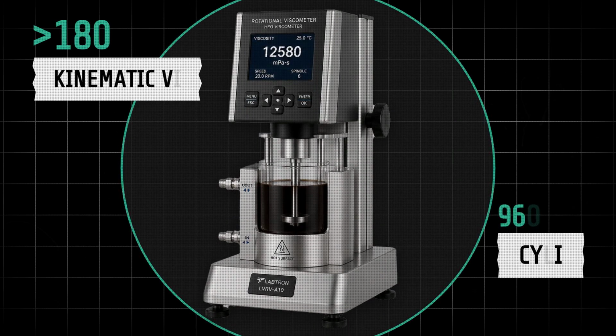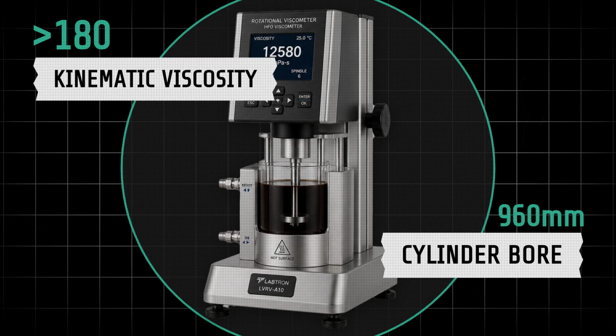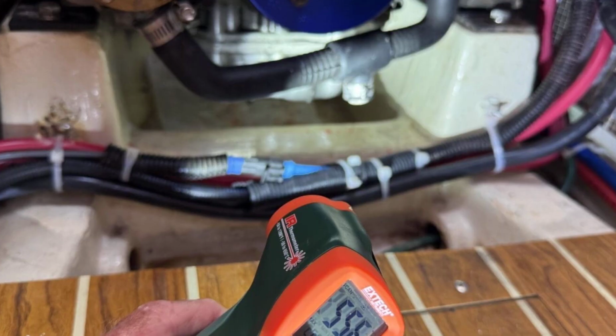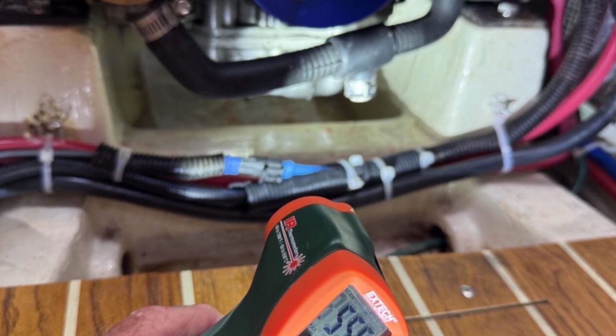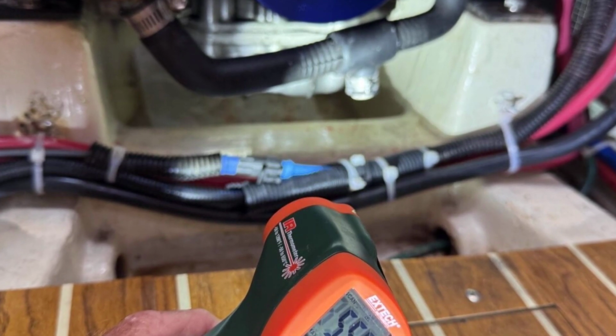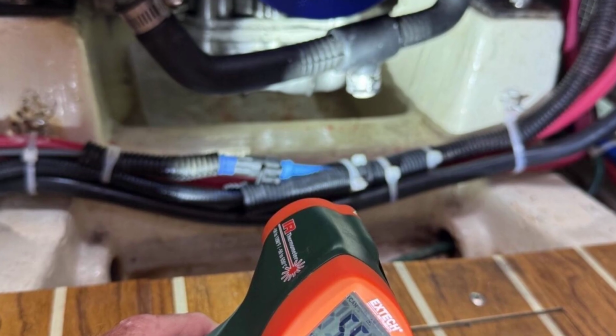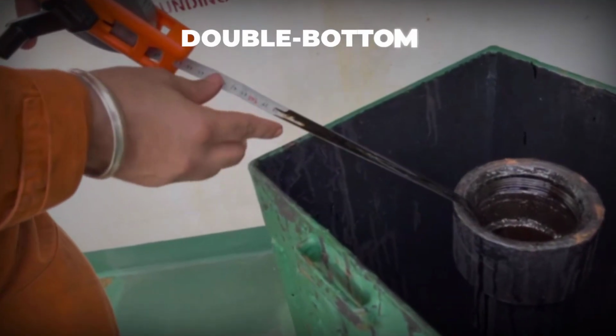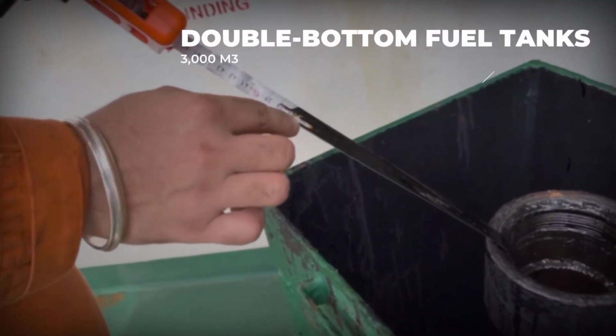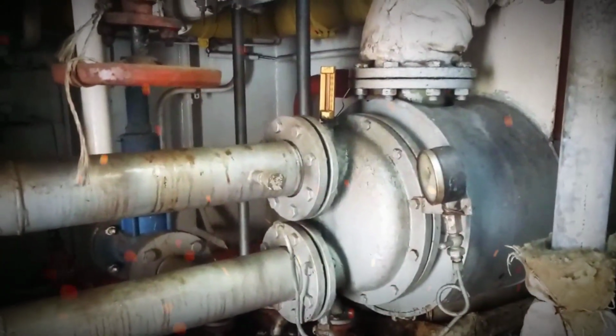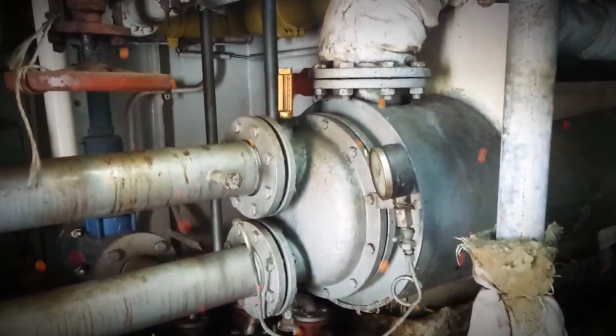With a kinematic viscosity exceeding 180 centistokes at 50 degrees Celsius, the fuel will solidify if its temperature drops to just 10 to 15 degrees above the surrounding seawater. To keep up to 3,000 cubic meters of this material pumpable, a ship must run a continuous high-energy heating chain.